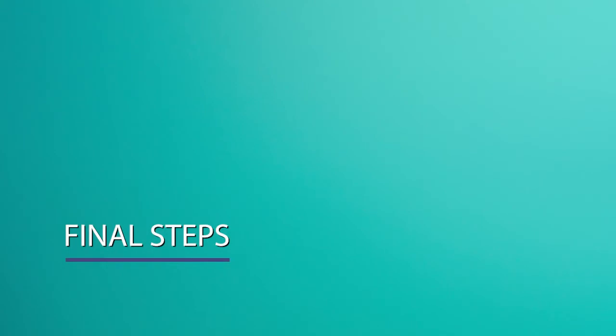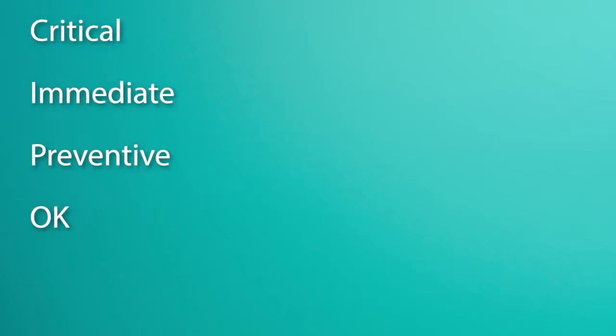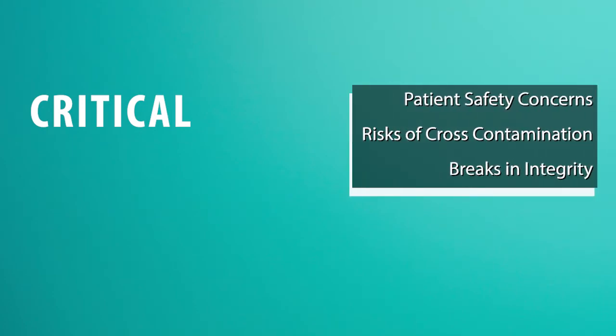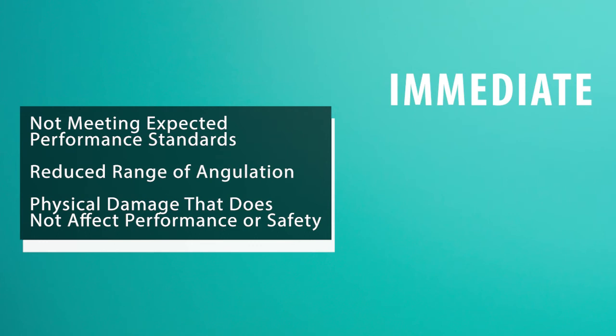At this point, complete any required paperwork and communicate any findings with a department manager. Results can be classified into one of 4 categories: critical, immediate, preventive, or okay. Critical is used to classify a probe that is not safe for patient use and one that should be removed from service. Example, a break in the integrity of the tip, the bending section, or the insertion tube, or even evidence of fluid invasion. Immediate can be used to describe a probe that is not meeting performance standards, such as not meeting angulation requirements, or a probe having a crushed or damaged insertion tube.